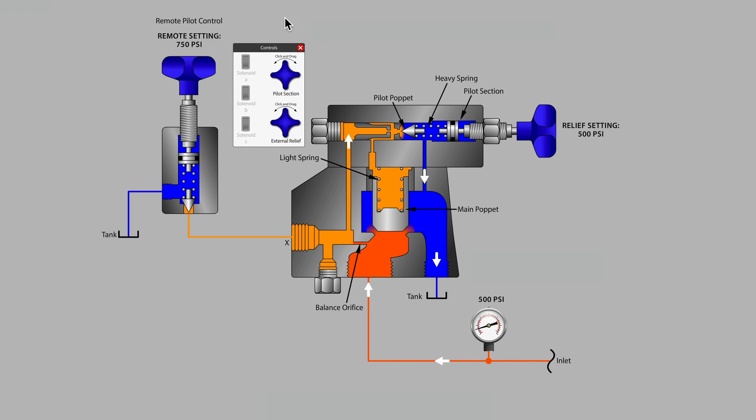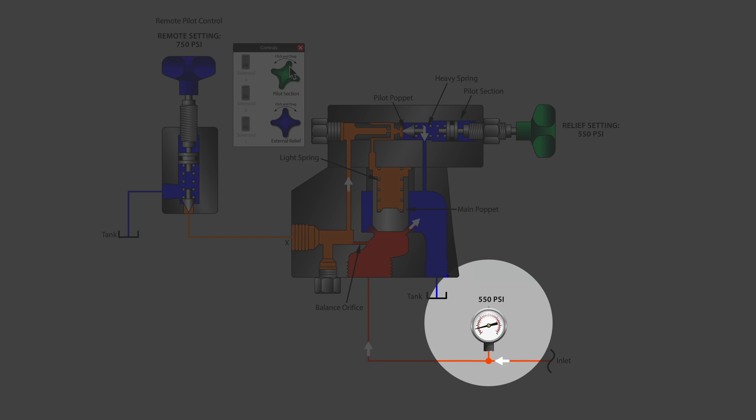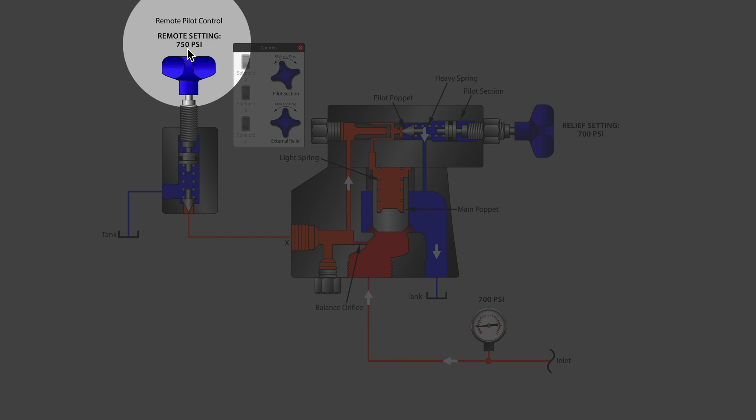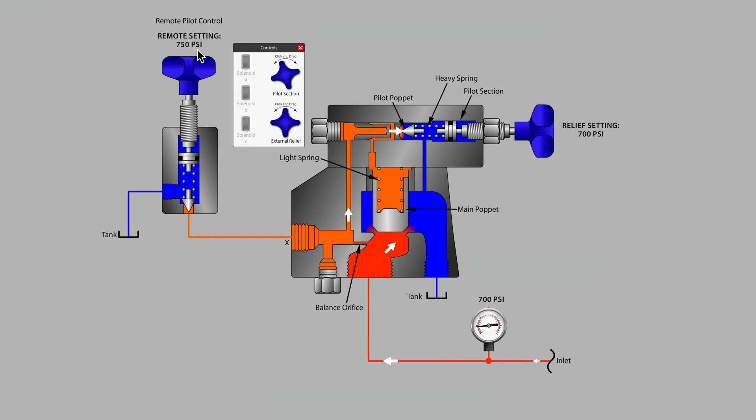Notice that the remote pilot section is set at 750. Well, let's start increasing the spring tension on the pilot section on the main relief and watch the pressure gauge. The pressure is going up, we are controlling the maximum system pressure. We're now at 700, but watch what happens as the system pressure passes over 750 psi.